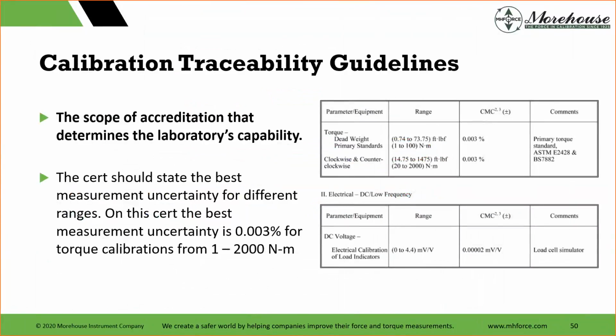So traceability guidelines: look at people's scopes. That's why people are accredited. Here, we upped our capability to 0.003%. Again, that's something we did. Our uncertainty is 0.0025. Our CMC is 0.003. That included test instruments and everything else under it. But the cert should state the best measurement uncertainty for different ranges. On this cert, best measurement uncertainty is 0.003 for torque calibrations from 1 to 2,000 newton meters.